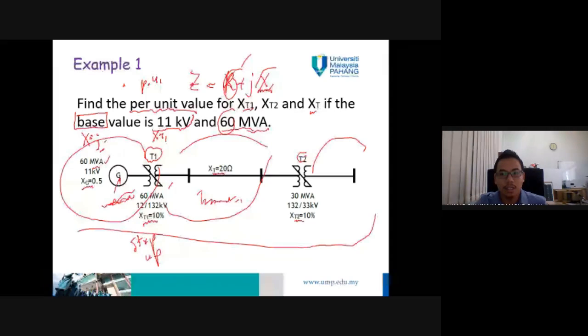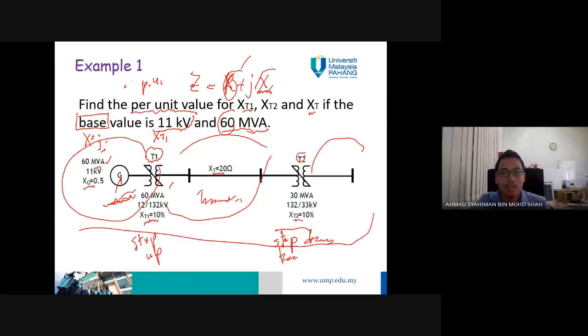So this is the step down transformer. Step down here is rated from 132 to 33 kV, and that's the ratio. The MVA given here is 30 MVA, while the reactance given for this transformer is 10%, which is equal to 0.1.